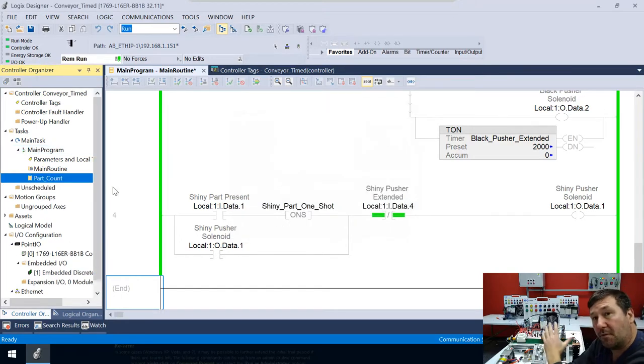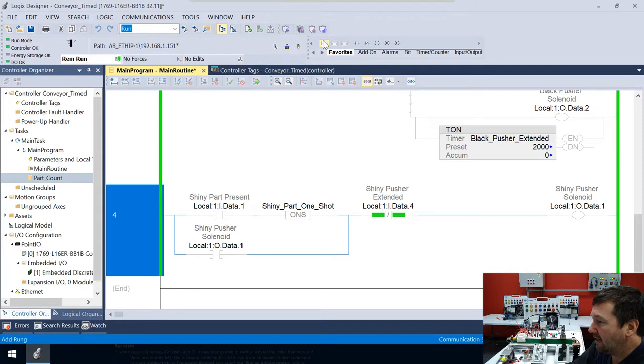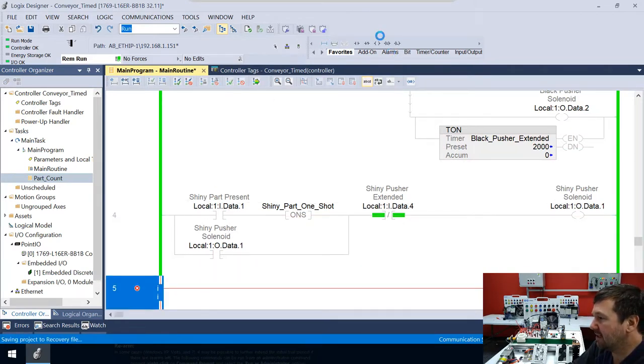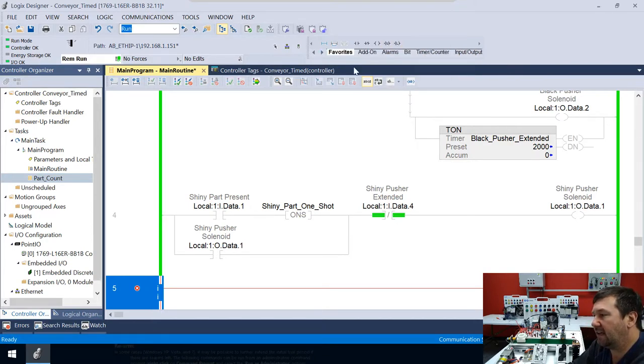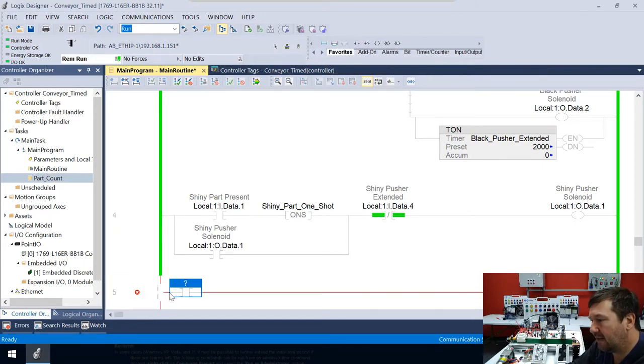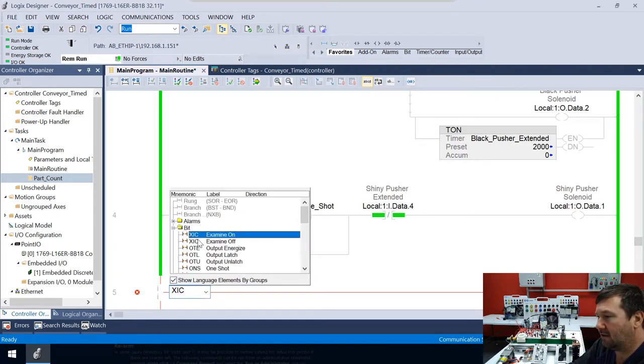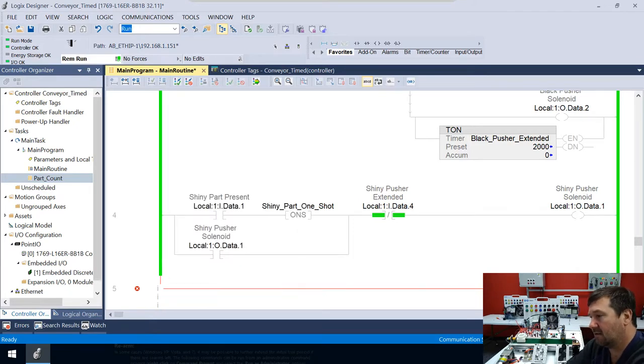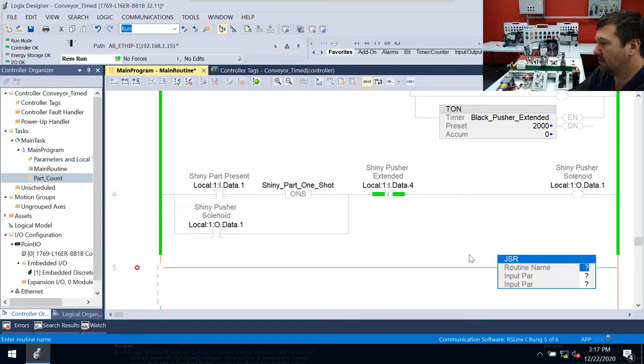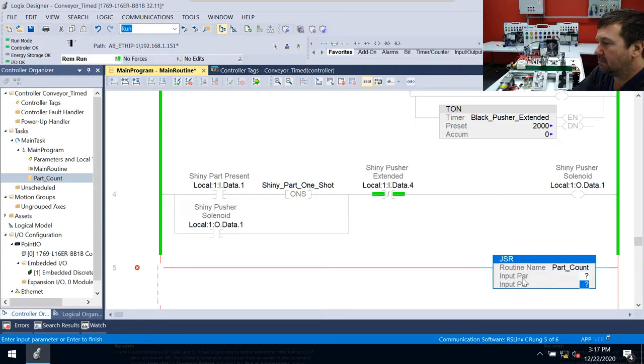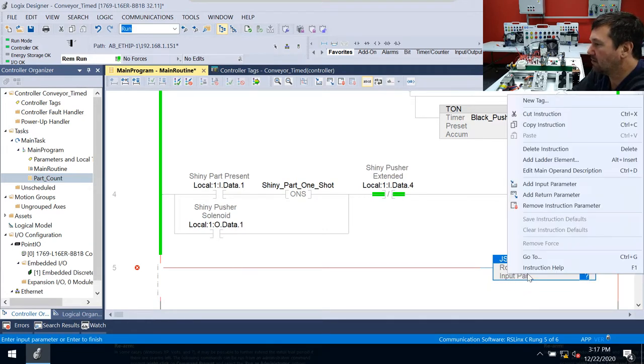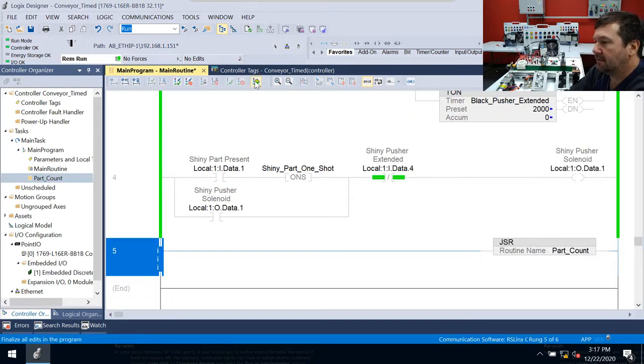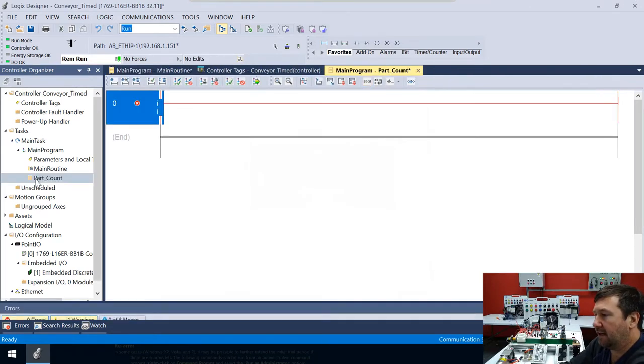And then if you remember from our basic start stop video on this, we need a JSR to get there. So let's go ahead and add that. Let's add another rung. And in this case, it's just going to be an unconditional JSR. And you don't actually have to go left and right in these. A lot of times, I'll just drag down anything and then highlight the symbol and hit enter. If you know the specific thing, like in this case, a JSR, let's just type JSR. That's going to be a jump subroutine. And in this case, we're going to jump to routine named part count. And we're not going to use any input parameters on this. So we are just going to remove our instruction parameters. Let's put that in there and then let's go down to our part count.